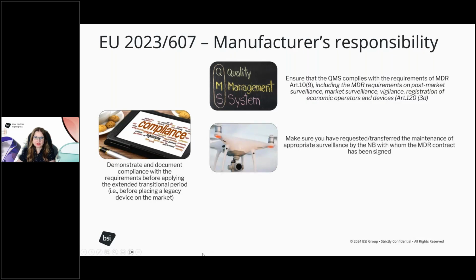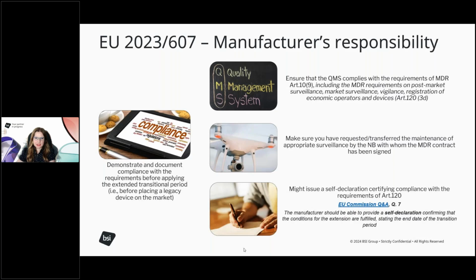Manufacturers, as we mentioned, need to have requested the notified body to maintain the appropriate surveillance for the legacy devices, or have transferred the responsibility for the appropriate surveillance from the directive notified body to the MDR notified body if they are different. And there is also the possibility for manufacturers to issue a self-declaration to declare compliance with the requirements of the amended Article 120, and this is covered by question 7 of the Q&A that the European Commission published to explain some activities or aspects of the amended Article 120. So as per the answer to question 7, manufacturers should be able to provide a self-declaration in order to confirm that the conditions for extensions are actually fulfilled, and they need to state what the end date for the transitional period for the devices is.